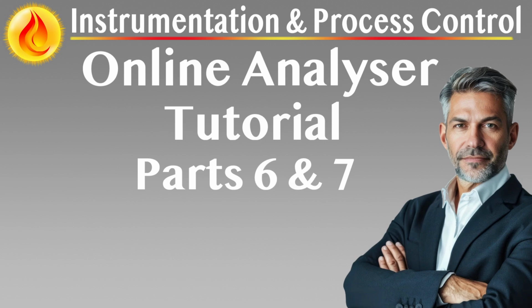Power supply and electrical utilities. Electrical power must be available in both normal and uninterrupted forms. Dedicated power circuits are required for analyzers and signal processing units, sample conditioning systems, heaters, pumps, chillers, HVAC and ventilation equipment, gas detection and alarm panels, and lighting, general and emergency. Uninterruptible power supplies, UPS, should be used for critical loads such as signal transmitters, communication devices, and safety systems. All power must be properly grounded and protected with overcurrent devices and surge suppressors.